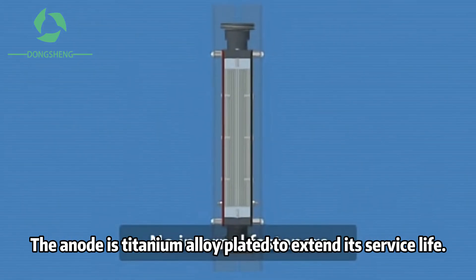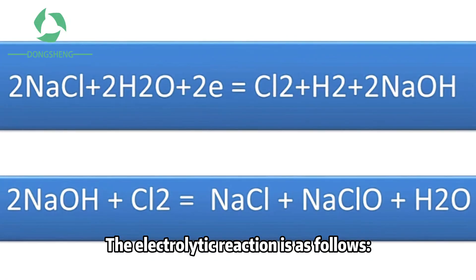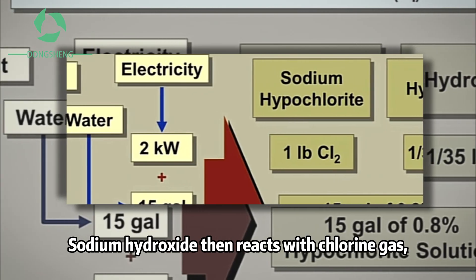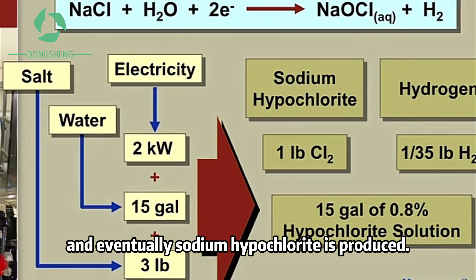The anode is titanium alloy plated to extend its service life. The electrolytic reaction is as follows: sodium chloride reacts with water to produce chlorine gas, hydrogen gas, and sodium hydroxide. Sodium hydroxide then reacts with chlorine gas, and eventually sodium hypochlorite is produced.